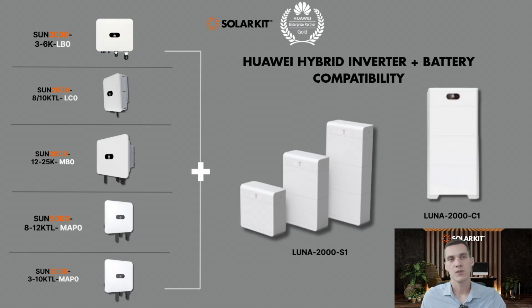Because only 33% of the nominal power can be used on one phase. However, if you have a one-phase system, then you don't have to worry about distributing the loads properly. You can just connect everything to that one single phase and worry about the overall load not exceeding the power output of the inverter, but it's way easier to calculate this way. These are for the single-phase devices, and then let's go to the MB0.